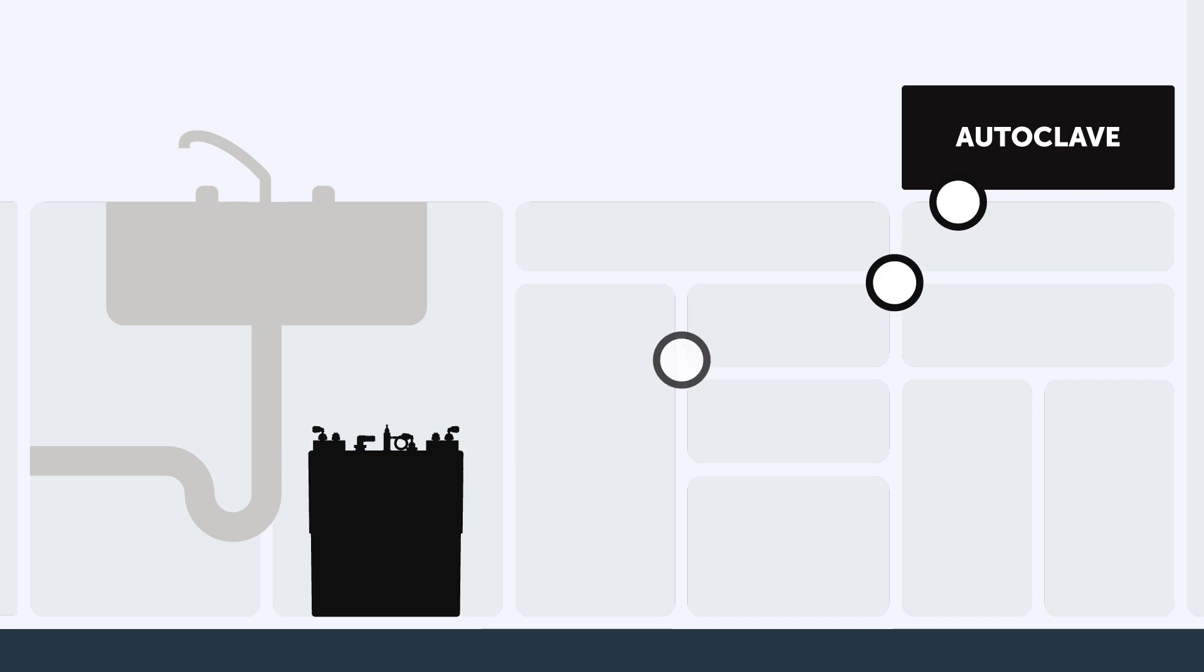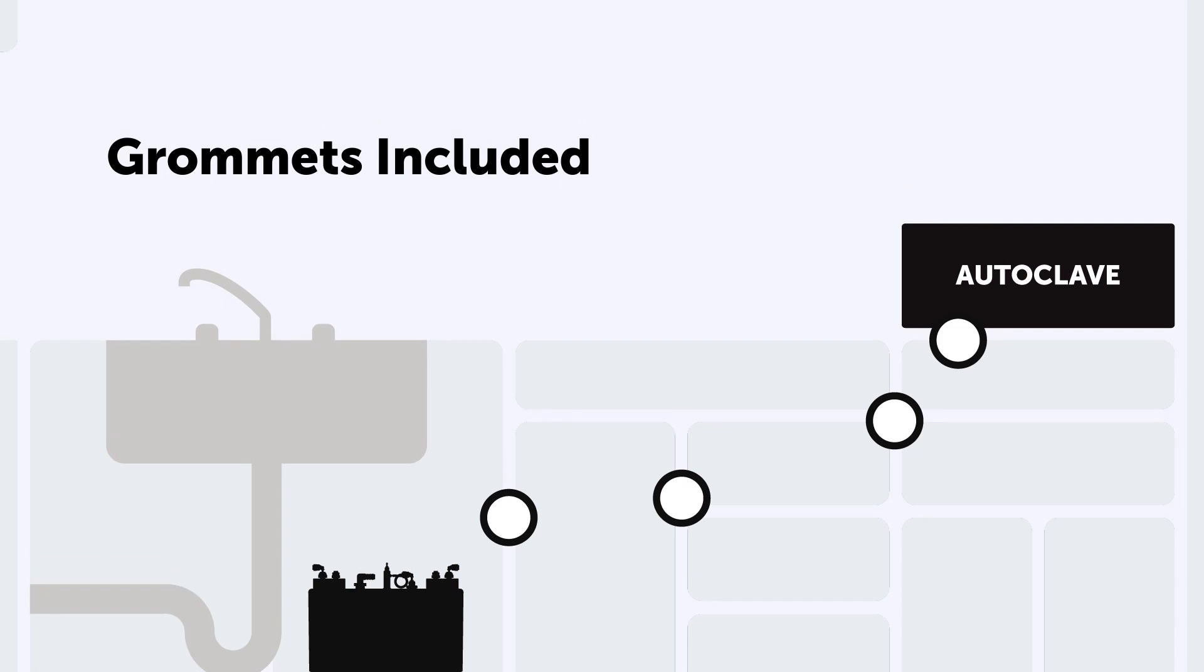In many cases, holes will need to be drilled through one or more partitions in order to get the tubing from the sterilizer to the VistaCool. In order to protect the tubing from kinking or damage, we've included grommets with each system, which are especially important to use when drilling holes in metal cabinets.